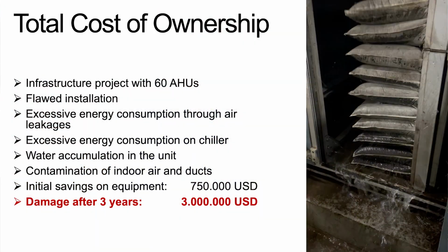You had water accumulation in the unit. There was 20 centimeters of water standing in the unit, before and after the filter section, so it's blowing contaminated water also into the airstream, of course. And we assessed that the client saved approximately $750,000 on the purchase side. And within the first 3 years, he ran into damages exceeding $3 million.